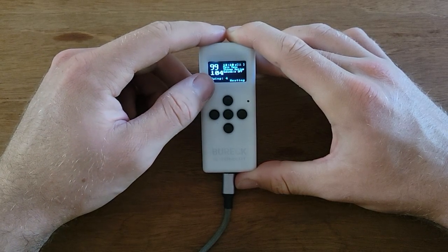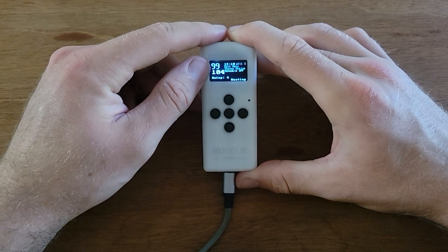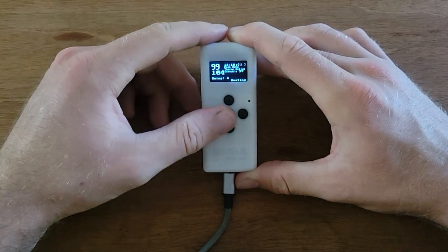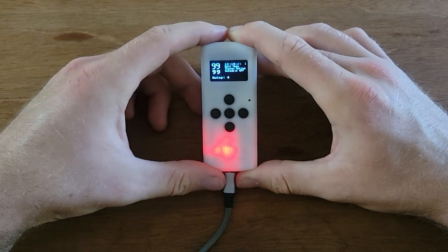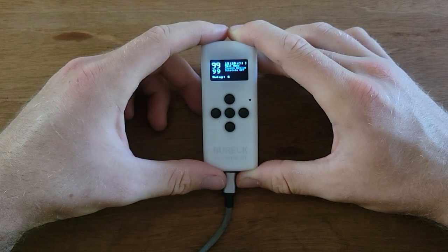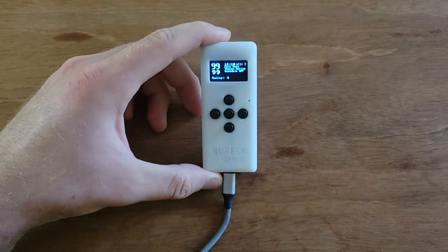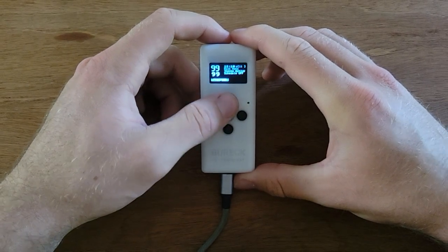So we have to be 4 degrees above the current temperature. The set temperature needs to be 4 degrees above the current temperature. Or the current temperature needs to be 4 degrees below the set temperature for heating to be initiated. And then once we get back to the set temperature, the heating will be turned off and it'll keep your heater off. So you can change this swing setting just like all the other settings. You go over, highlight it, and go up and down.